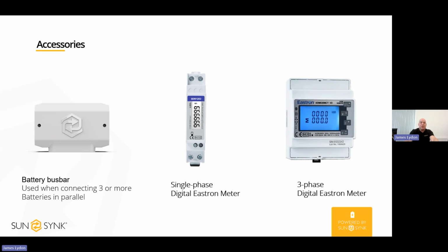If there's more batteries, you can parallel the bus bars. It comes with a little copper connection piece, so you can have more bus bars connected together. So you'd have the included battery cable going to the bus bar, and then from the bus bar to the inverter, that cable size is dictated by the size of the inverter. If someone's using a 3.6 or a 5 kilowatt hybrid inverter, you will be fine using 25 mil square cabling from the bus bar to the inverter, because the maximum that inverter is going to do, if it's the 5 kilowatt, is 120 amps.